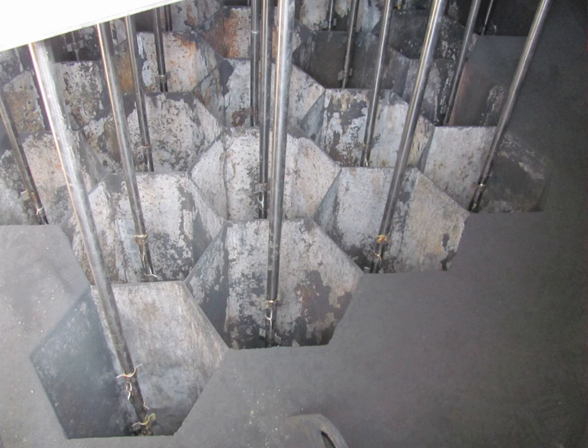Thin dust layers and high resistivity dust especially favor the formation of back corona craters. Severe back corona has been observed with dust layers as thin as 0.1 mm, but a dust layer just over one particle thick can reduce the sparking voltage by 50%. The most marked effects of back corona on the current-voltage characteristics are: reduction of the spark-over voltage by as much as 50% or more; current jumps or discontinuities caused by the formation of stable back corona craters; and a large increase in maximum corona current, which just below spark-over corona gap may be several times the normal current.